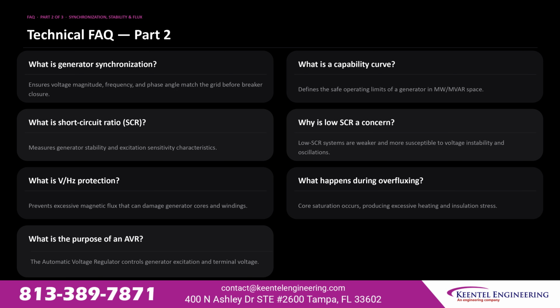What is short circuit ratio? It measures generator stability and excitation sensitivity characteristics. Why is low SCR a concern? Low SCR systems are weaker and more susceptible to voltage instability and oscillations. What is Volts-per-Hertz protection? It prevents excessive magnetic flux that can damage generator cores and windings. What happens during overfluxing? Core saturation occurs, producing excessive heating and insulation stress. What is the purpose of an AVR? The automatic voltage regulator controls generator excitation and terminal voltage.